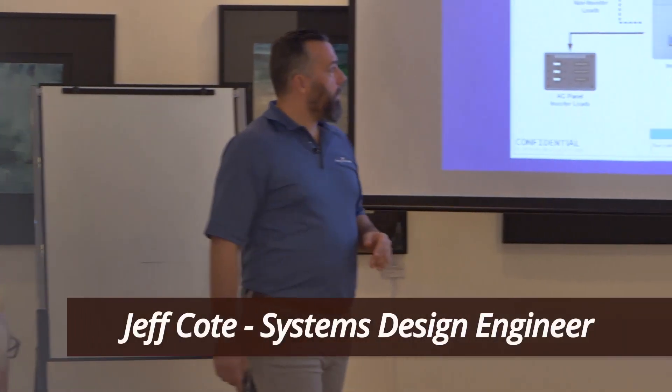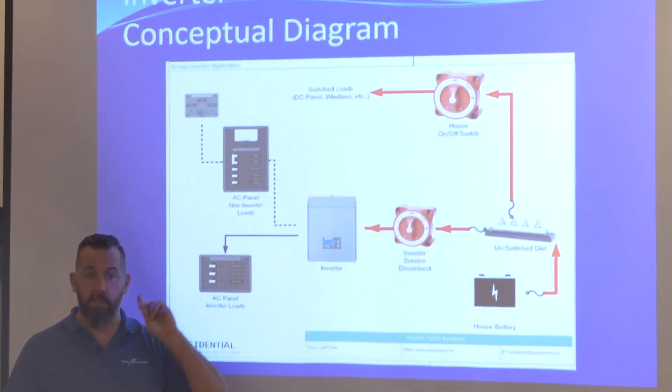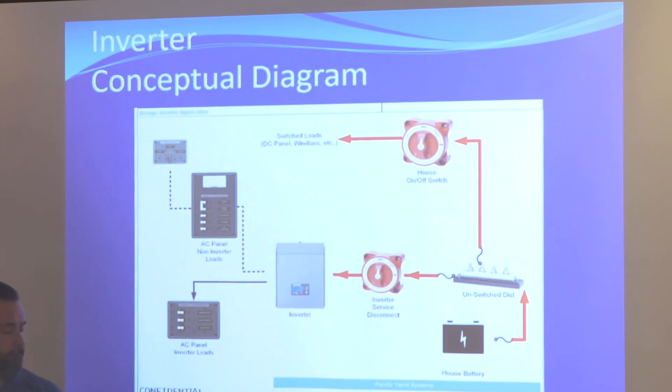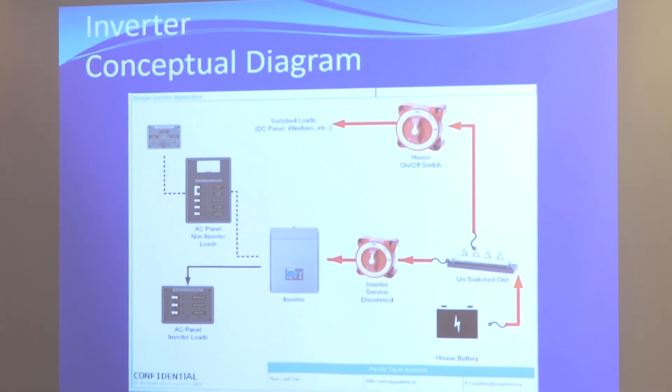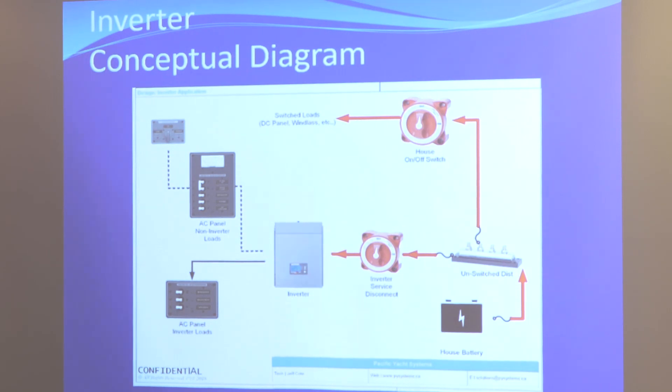Next we're going to talk about inverter. So now we've got an inverter right here in the middle. This is not an inverter charger, this is an inverter. The biggest issue when you troubleshoot an inverter, honestly, is remember what I said yesterday: inverters have no ability to say no. They will do whatever you ask of them.